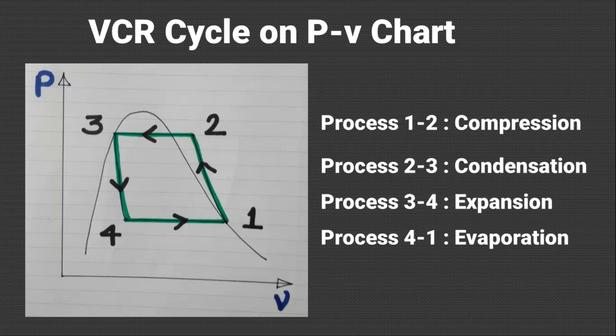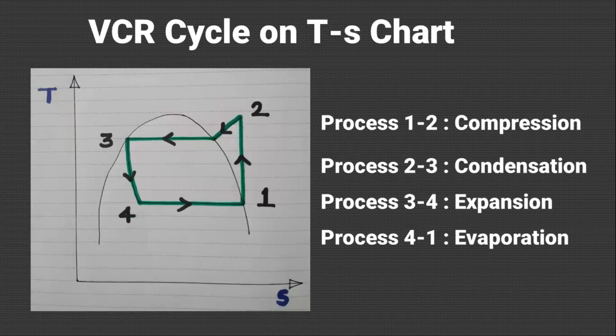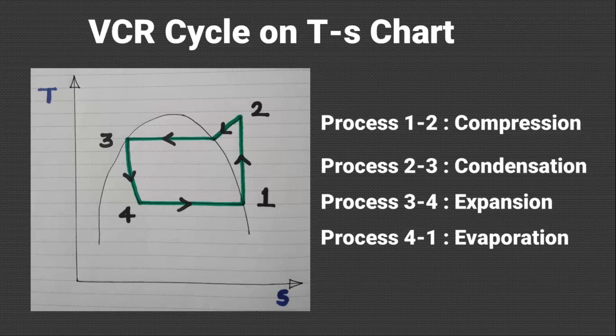The same vapor compression refrigeration cycle on the TS chart is shown in the next slide. Here on the horizontal axis there is entropy and on the vertical axis there is temperature. Process 1 to 2 shows the compression. The cycle we are discussing is the theoretical cycle, so compression is assumed to be isentropic, and the compression process is shown as a vertical line from 1 to 2. At state 2, the refrigerant vapor is in a superheated stage. Such superheated refrigerant is then cooled sensibly to saturation temperature first in the condenser, after which the refrigerant starts to condense. This saturated liquid refrigerant is then throttled through the expansion valve, shown by process 3 to 4, and process 4 to 1 is evaporation of refrigerant at constant temperature.